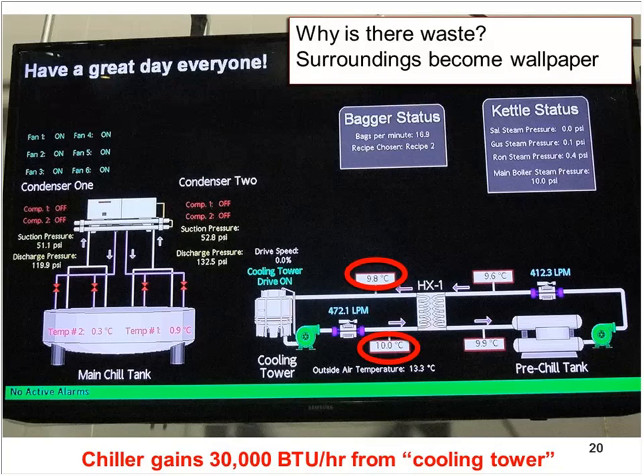This information was available to those 200 people who passed by every day, but they never knew that the most efficient thing to do, when they ran this particular product, would be to just turn off the entire system. That would be the most sustainable thing to do. That's a particular reason for the waste, and you can eliminate pumps and fans of this entire system. If you're just looking at more efficient pumps and fans, you sometimes miss the greater point.